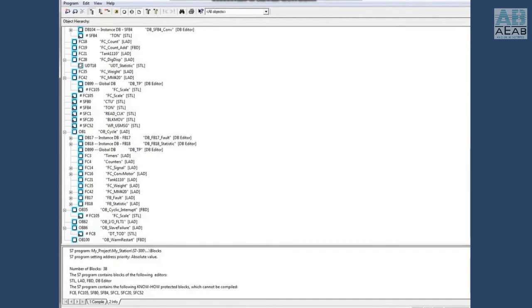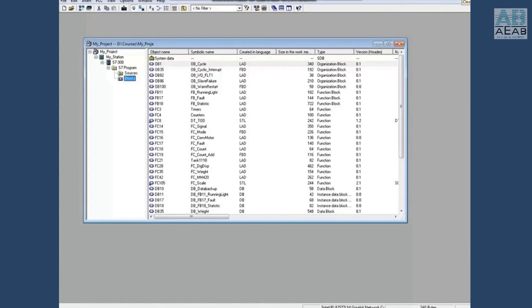When OB1 was opened, the FB18 and DB18 interfaces were automatically updated and we fixed the call to FC4. The check block consistency tool can generally fix the interface issues with FBs, DBs, and UDTs, but it cannot fix the interface issues with FCs - we have to do that. This concludes this video. Thanks for watching.